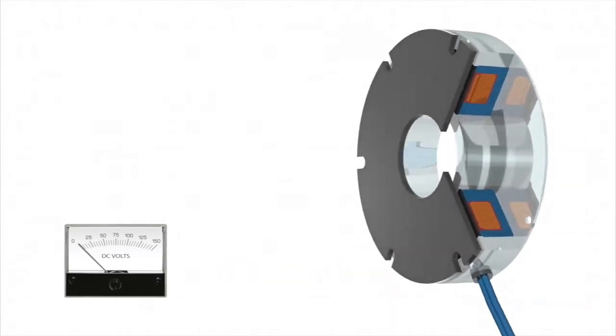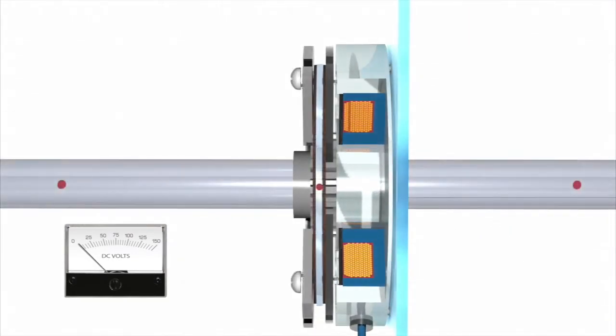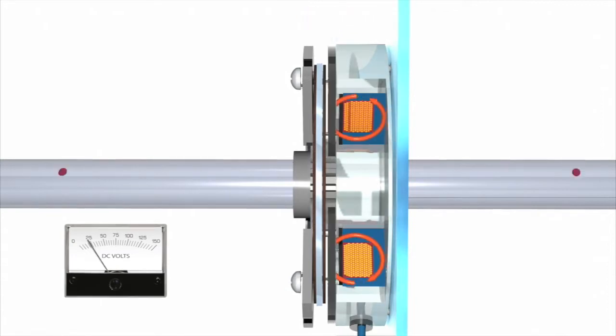This flux travels through the small air gap between the pressure plate and the field coil, attracting the pressure plate to the coil and compressing the springs, releasing the friction disc so it is able to rotate.